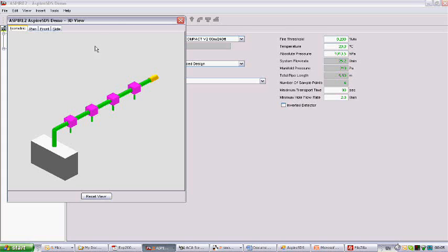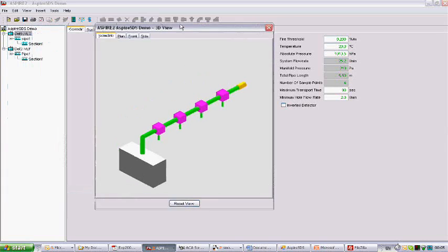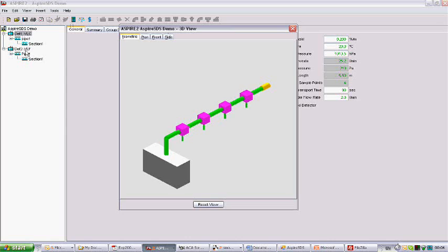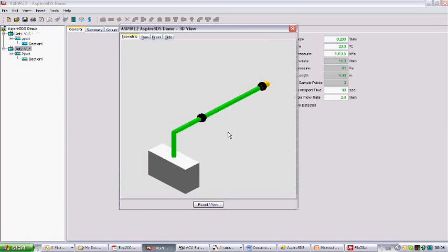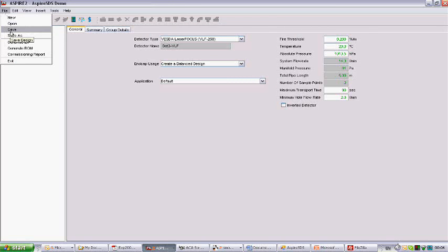And it's this arrangement that we effectively want to drop into our FDS model with the relevant transport time and flow figures for each hole. Of course we can also view the 3D representation of the VLF detector which provides 2 sampling holes in the ceiling. All this data is simply saved and can be imported into our FDS model.